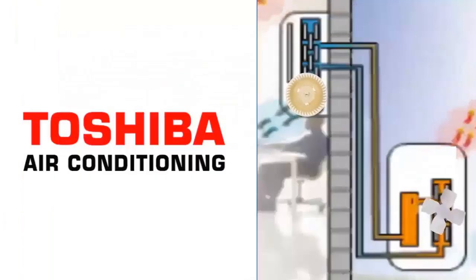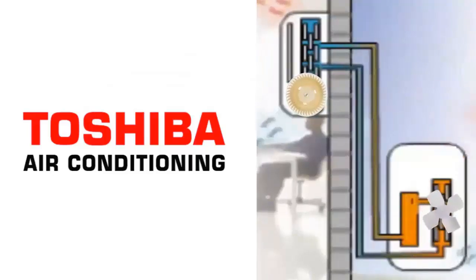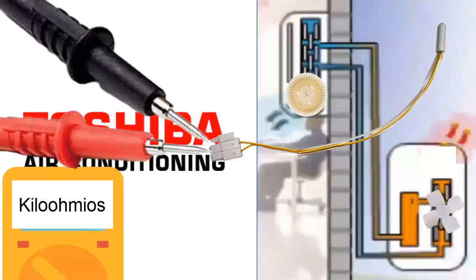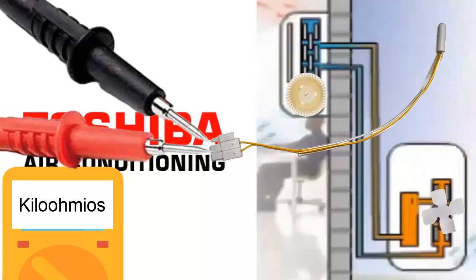6. If the error persists, turn off the unit, disconnect the sensor, and measure its electrical resistance with a multimeter set to the kilo scale. The measured value should never be 0 or infinite. When rubbing the sensor with your hand, the resistance value should decrease.